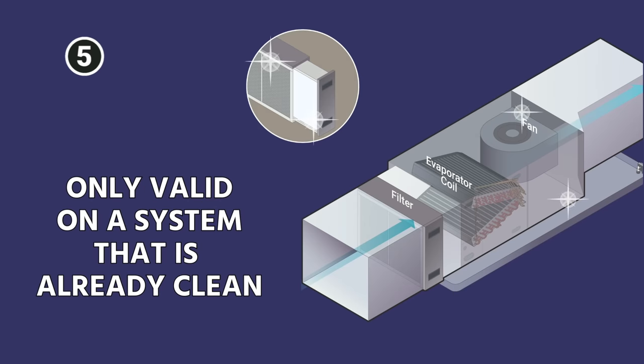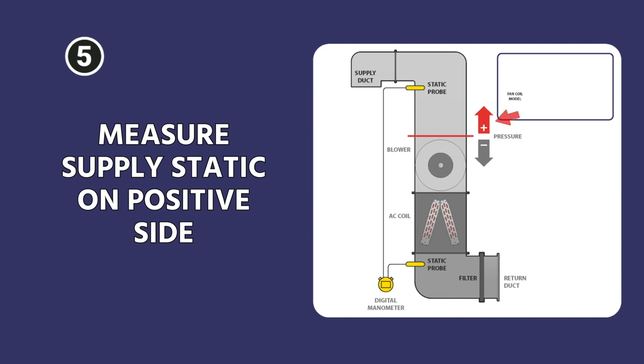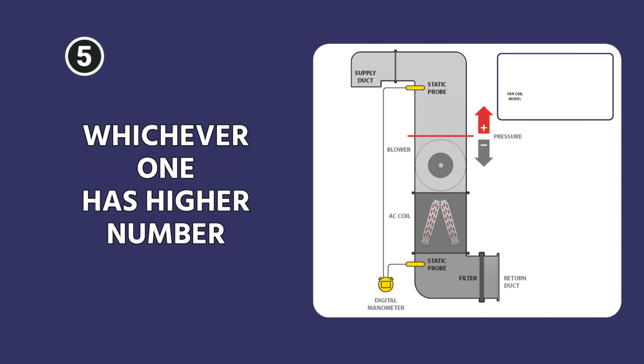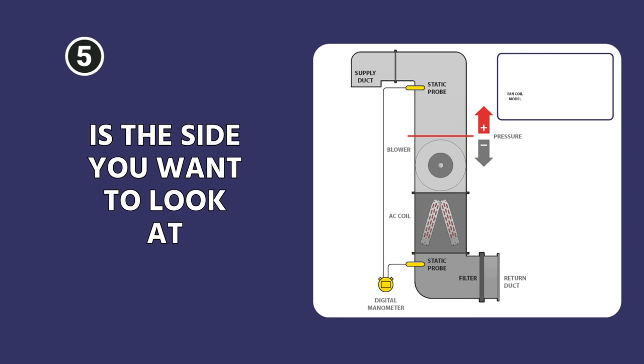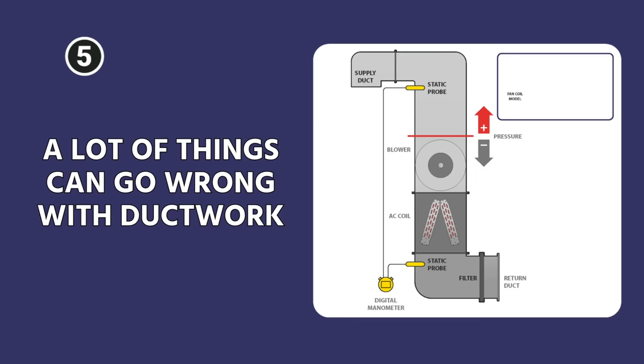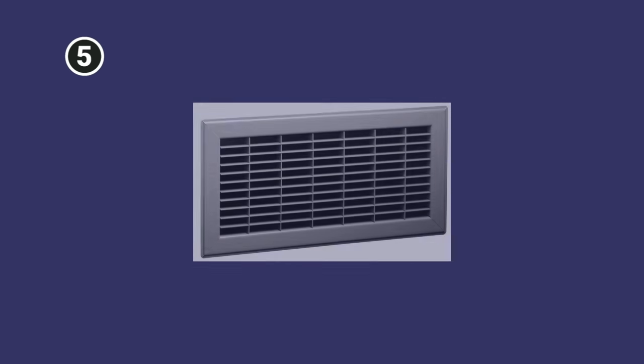This is only valid on a system that is already clean and once you already know the system has been set up for proper settings. Measure your total external static — measure your supply static on the positive side and your return static on the negative side. Whichever one has the higher number is the side that you want to look at. Look for things like kinked ductwork, ductwork that's improperly strapped or undersized, or even someone pushing a couch up against the return or shutting off a bunch of registers in the house.